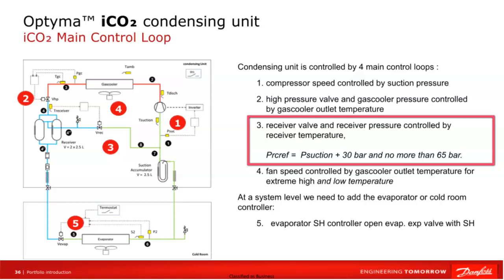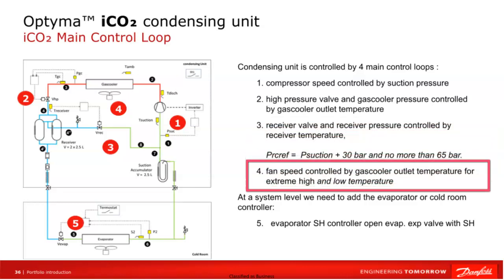In case of high outdoor temperature, transcritical operation, the gas relief valve maintains the pressure difference between receiver and suction at plus 30 bar. The gas bypass valve is closed when we have low outside temperatures. Fan speed is controlled by the gas cooler outlet temperature, especially in extreme high and low temperatures.